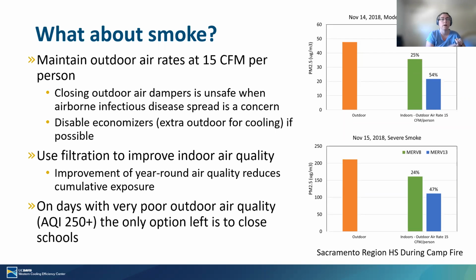Filtration helps both indoor air quality and smoke, from a respiratory disease perspective and smoke. So again, that's why this filtration is so important. And I just have an example here. This is back from a fire in Northern California, the Camp Fire back in 2018. This was 6 classrooms we were monitoring during the Camp Fire in the Sacramento area. And 3 classrooms had MERV 8 filters and 3 classrooms had MERV 13 filters, and both were being ventilated at this rate of 15 CFM per person.